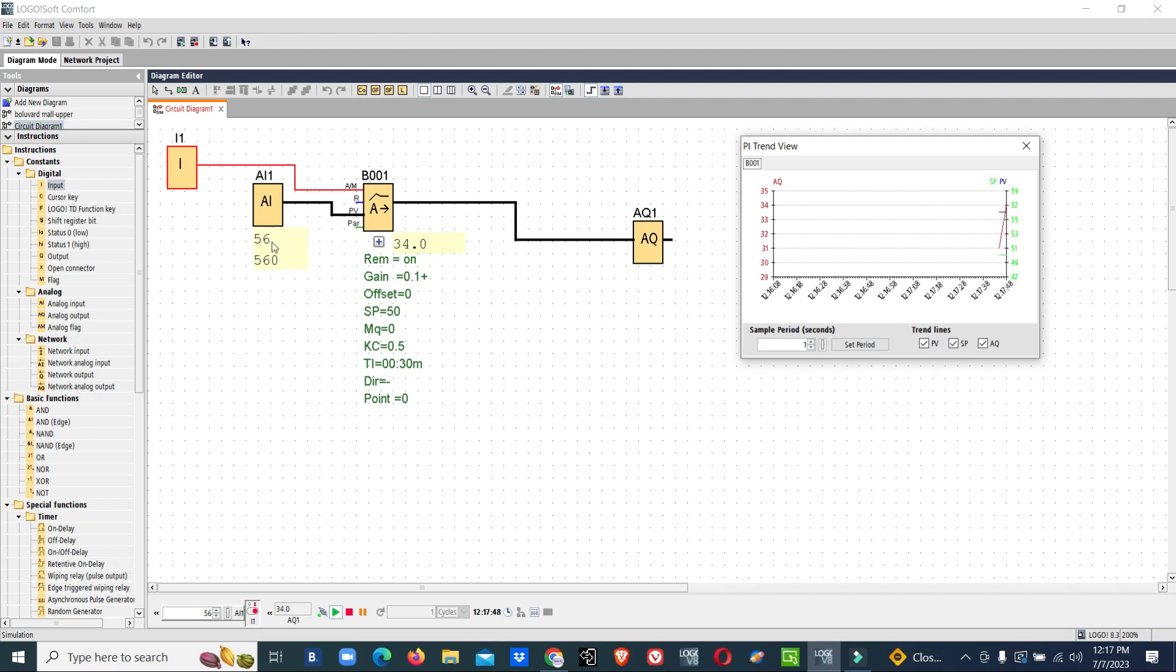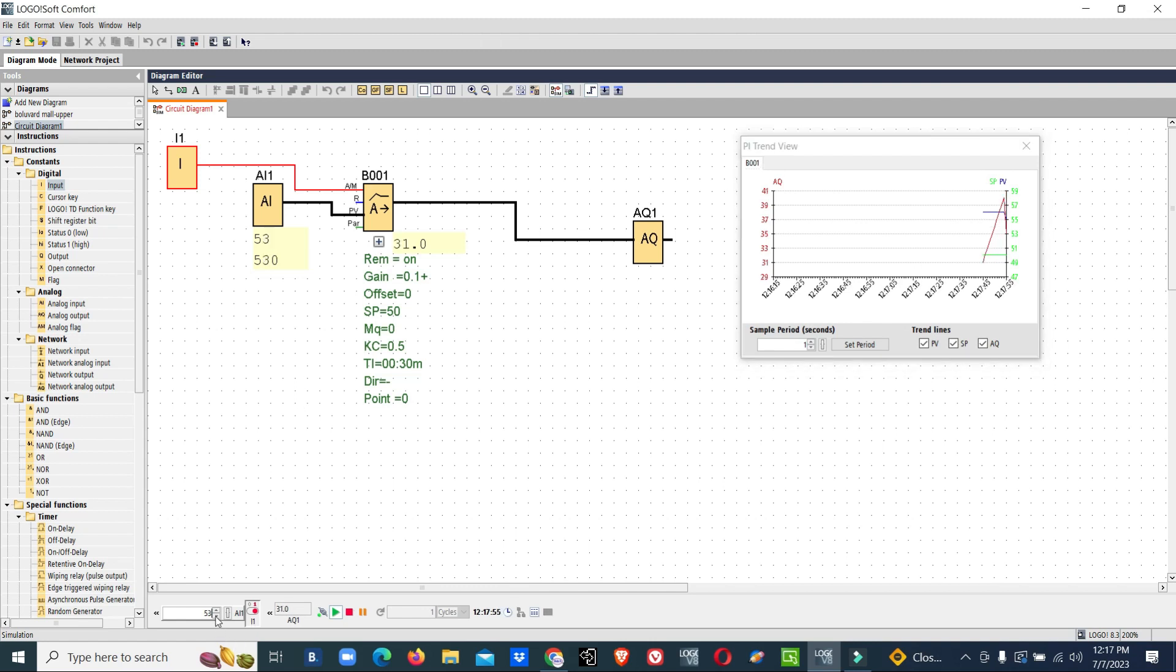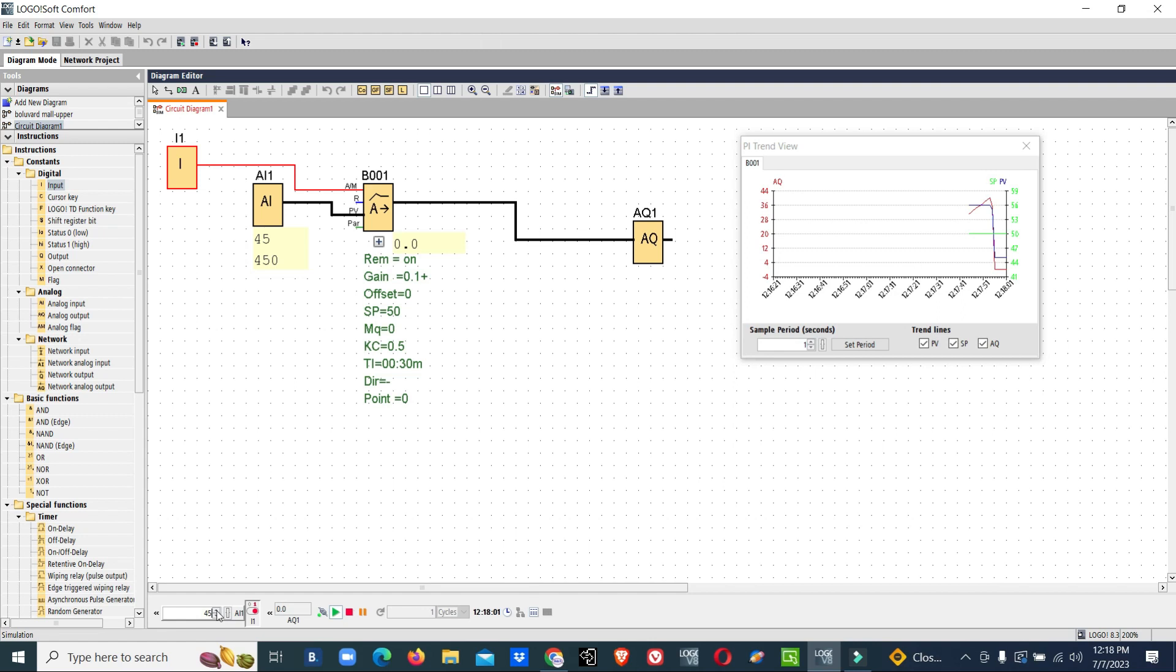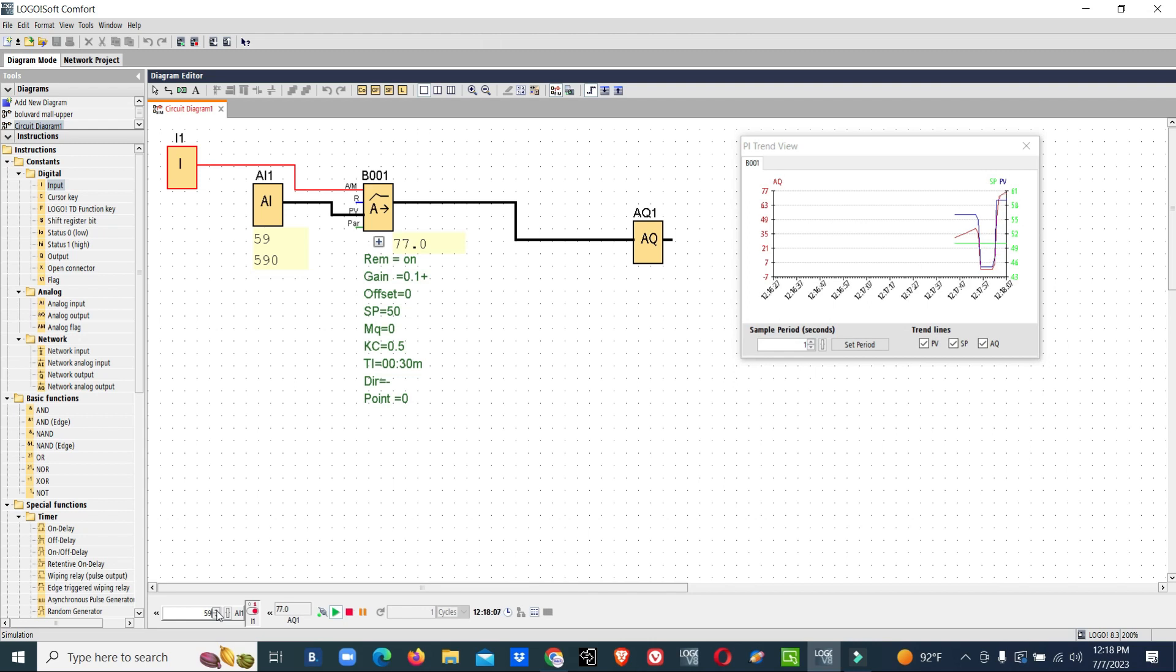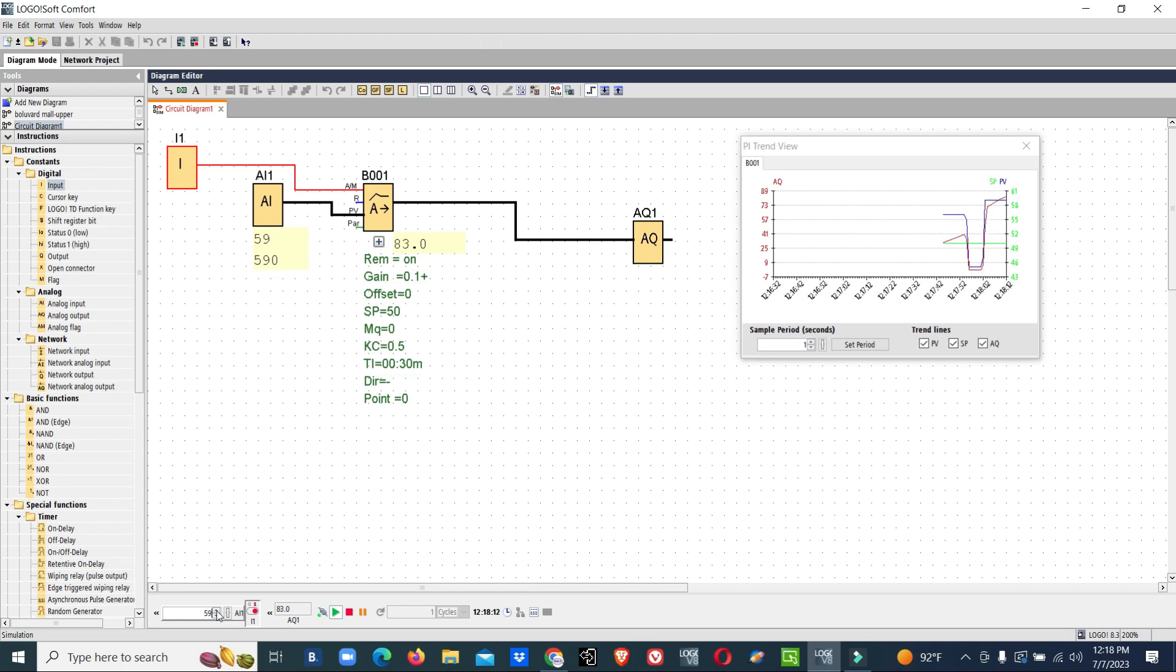Now you can see our set value is 50 and the value is 56, so the analog output is enabled. Once this value goes below, the output value also will come to zero. Once the value goes up, the analog output will enable. This is the difference between upwards or forward PID and downwards or reverse PID.